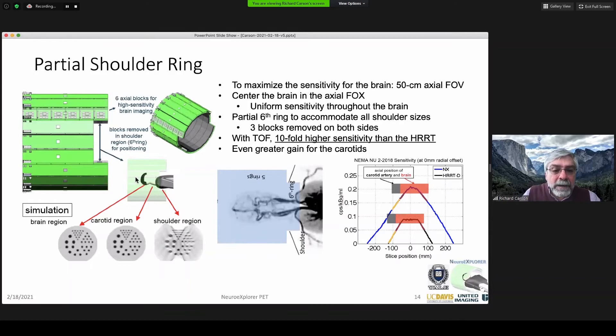To maximize sensitivity, we want to position the patient in the center of the field of view, with a 50-centimeter long field of view. The challenge is shoulders. We've designed a partial shoulder ring — the last ring in the scanner has a notch to allow the shoulders to be placed in, centering the brain in the field of view. That combination of intrinsic sensitivity, long axial field of view, and great time-of-flight predicts tenfold higher sensitivity. The raw sensitivity profiles comparing the NX and our current HRRT show a big increase in the center and an even bigger increase at the edges where the carotids are.